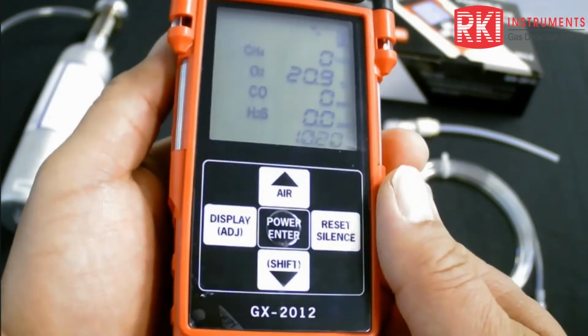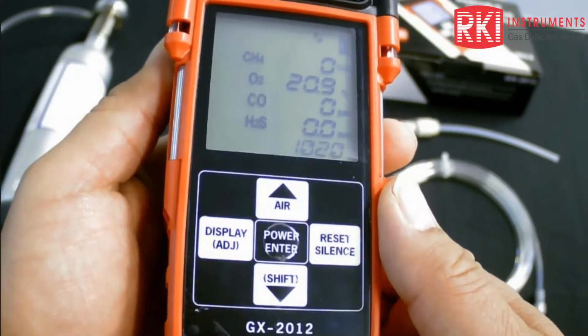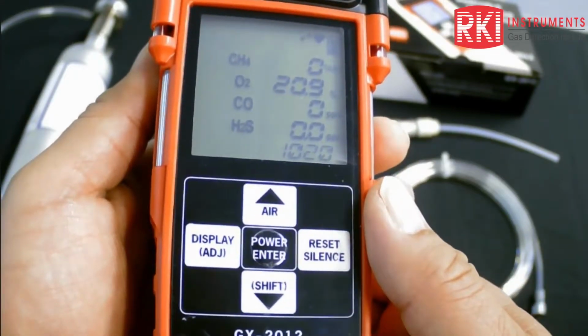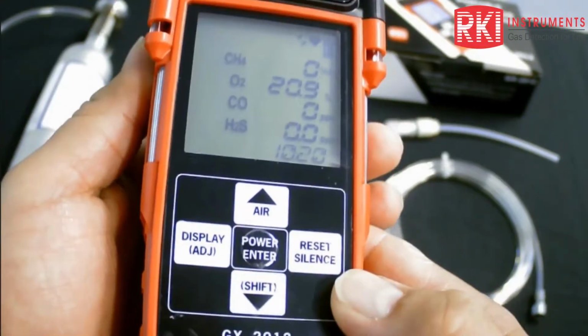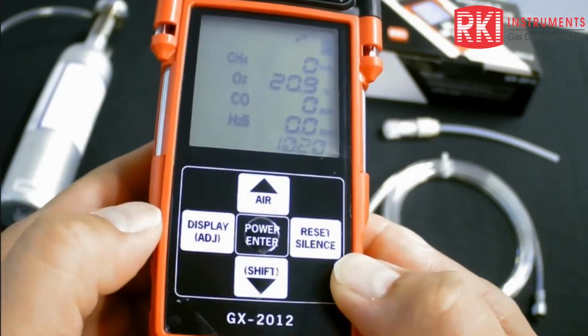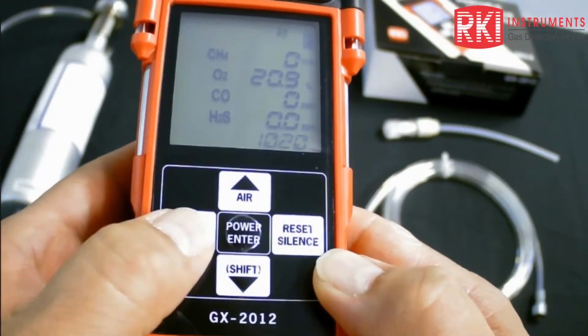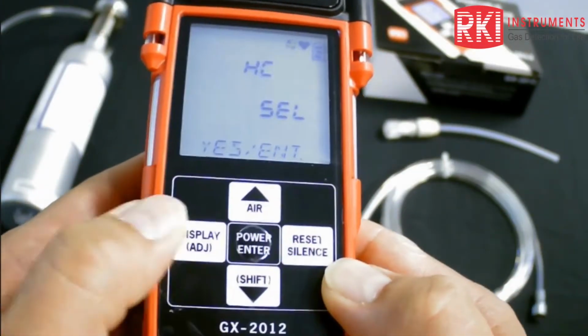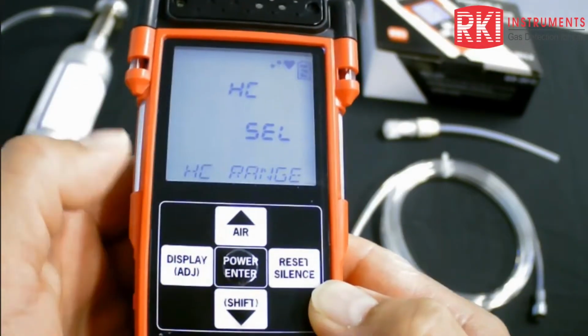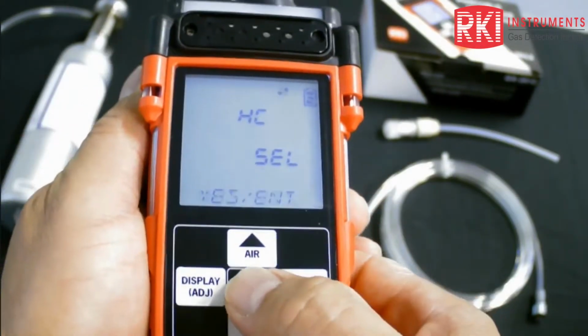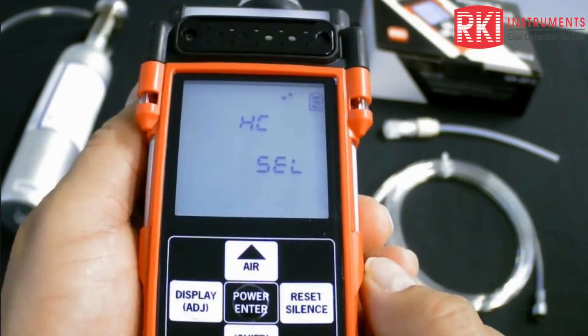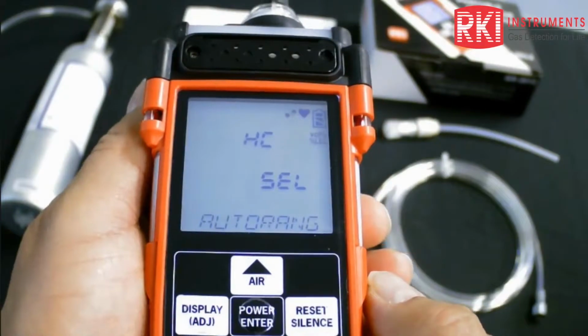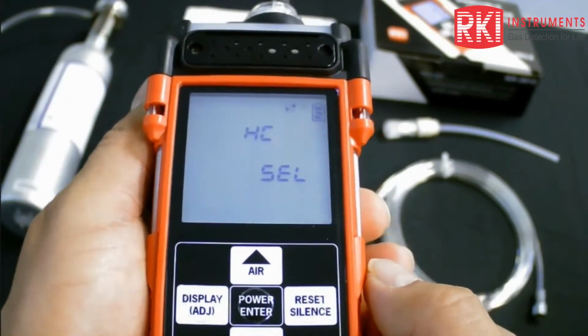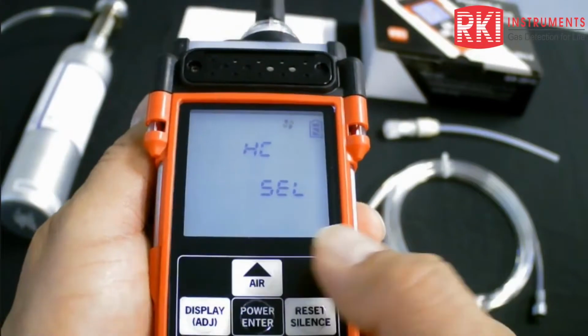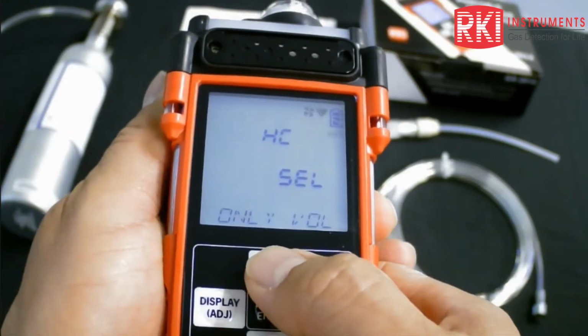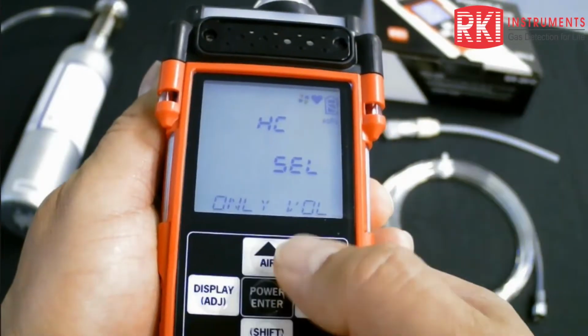All right. So one of the things that you can do, as I mentioned before, is to go into % by volume only, or select that. And you do that by pressing this display button. The display button gives you several things that you can do. If we press this display button first, it says HC hydrocarbons, select HC range. Okay, if I press enter right here, right now it's at auto ranging. So that's the normal setting for a 5 sensor configured unit, or at least a LEL and % by volume configured unit. And if I press my up and down arrow keys, I can make that only vol. So that's what you would want to do and lock that in.